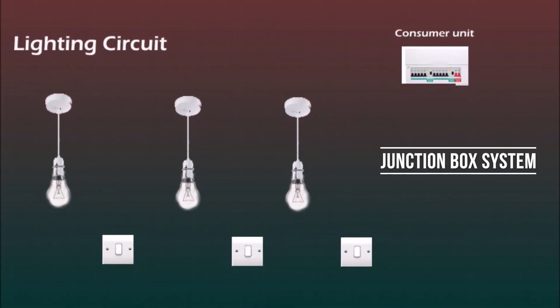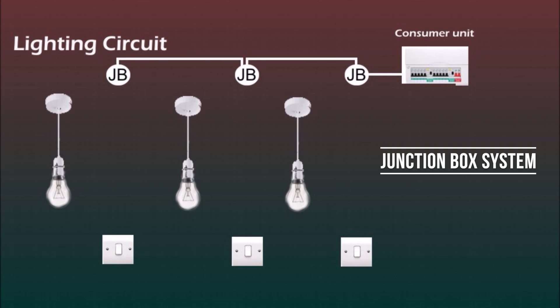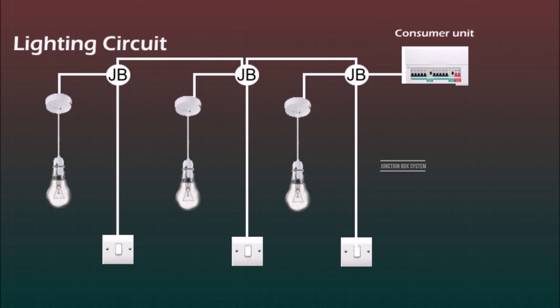The second method is a junction box system. So we've got three lamps not necessarily with the ceiling rose, three switches for each lamp and three junction boxes somewhere inside the ceiling. Each of these junction boxes work like the previous ceiling rose and the live wire from the switch is fed from there. In both of these systems you have only live wire at the switch, not the neutral.